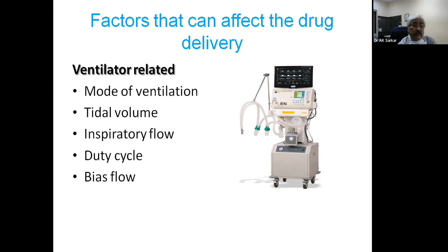First, the mode. We should always go for volume control ventilation. If the patient is on, say, SIMV mode or pressure support, you have to change this to volume control, provided the patient has low compliance and low resistance. And tidal volume should be at least 500 or above. If the patient is on 6 ml per kg body weight, for 70 kg, that is around 400. But you have to increase the tidal volume during the time of nebulization. This is important, and inspiratory flow should not be too high. It should be between 30 to 50 liters per minute.